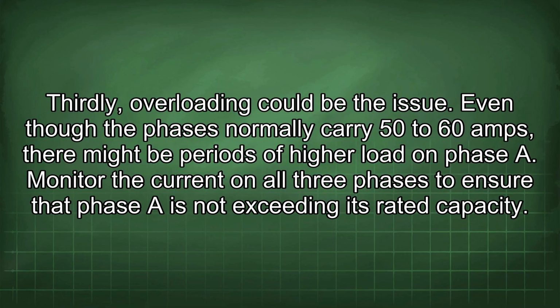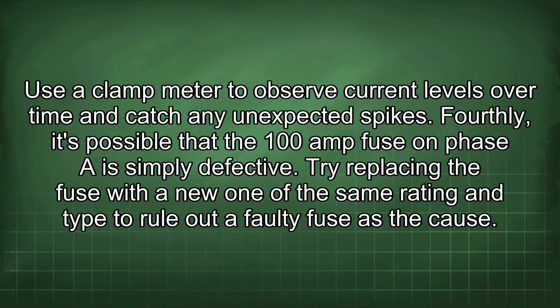Thirdly, overloading could be the issue. Even though the phases normally carry 50 to 60 amps, there might be periods of high load on phase A. Monitor the current on all three phases to ensure that phase A is not exceeding its rated capacity. Use a clamp meter to observe current levels over time and catch any unexpected spikes.